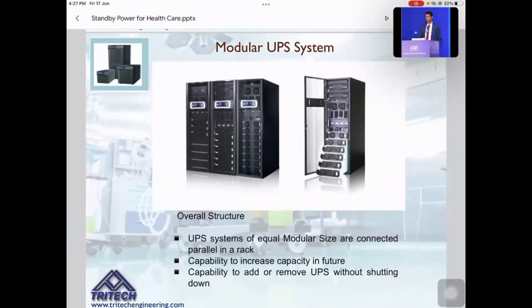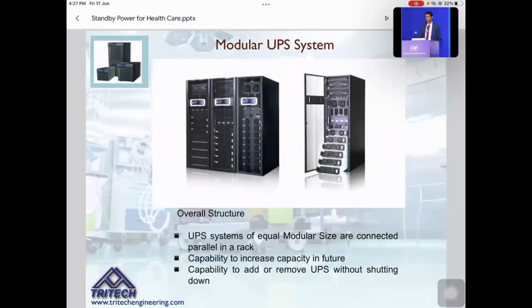So most of the modern projects, I mean the new projects whichever we are having, many of them are having a lot of modular UPS systems compared to the conventional system. So we have two types of UPS systems. Basically the conventional one, which has been available for a long time, which works on an N+1 configuration, and we have the modular UPS system, which has a fraction of the backup as an additional module. And it has the extra flexibility of increasing the capacity later, or if you want to replace a damaged unit, that is also much easier. So from a maintenance point of view also, we have some advantages for the modular UPS system. This is what I'm going to highlight.